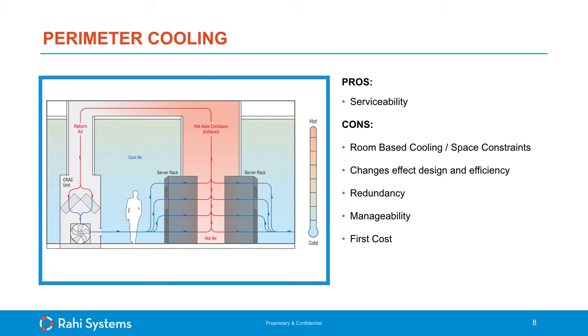And just to quickly touch on containment, hot and cold aisle containment do contribute greatly to the cooling efficiency by providing proper cooling to the IT load and returning the hottest IT exhaust air back to the cooling units. So, looking at the IT trends, you have 20 kW per server rack on upward. Containment is always, and should always, be looked at and applied in all of these types of cooling scenarios.